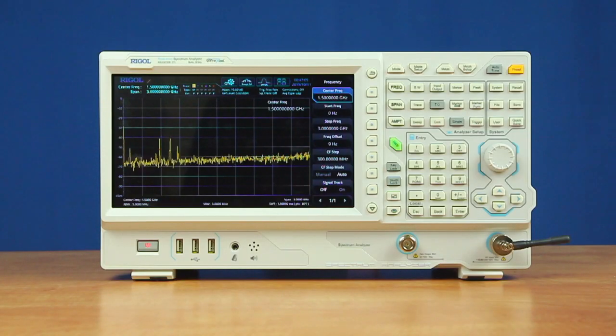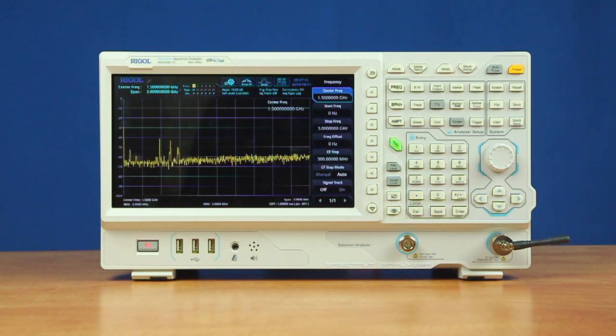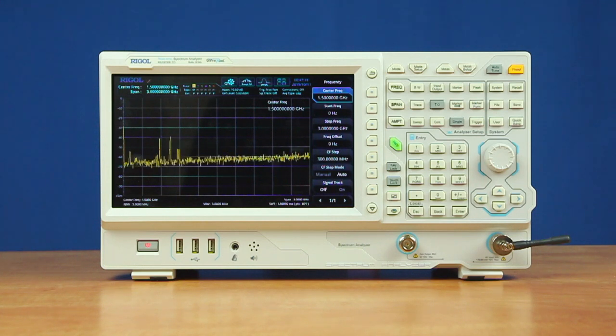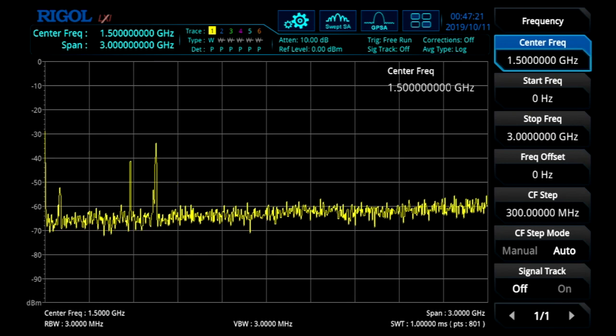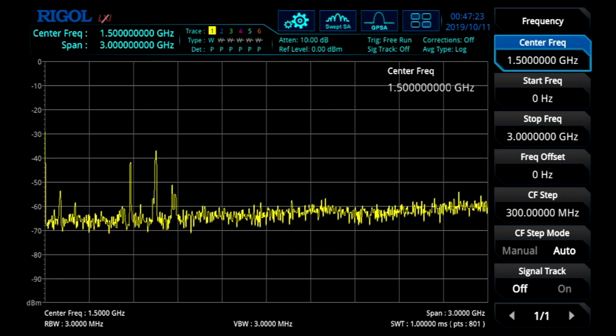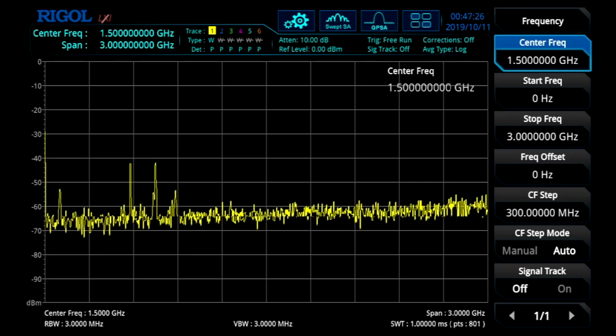In general purpose mode the instrument operates as a swept spectrum analyzer, allowing it to sweep across the entire frequency range. In general purpose mode we can set the resolution bandwidth down to 1 Hz and a noise floor down to negative 161 dBm with the optional preamp. We can also scan the full 3 GHz span with just one millisecond, as you can see here on our display.